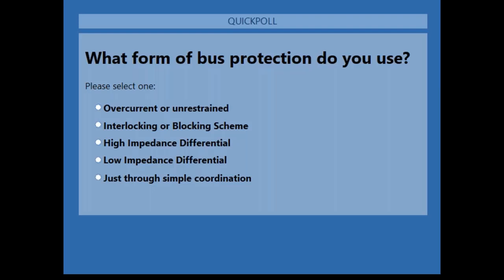Some of the arc flash detection techniques we're going to talk about are zone interlocking with relays and bus differential protection. Our concentration is going to be on bus differential protection. We're also going to talk about using light sensors, because, as we mentioned, one of the first things emitted by arc flash energy is light. That's the fastest thing we can detect, right? Nothing is speedier than light, so it can offer us fast detection of arc flash.